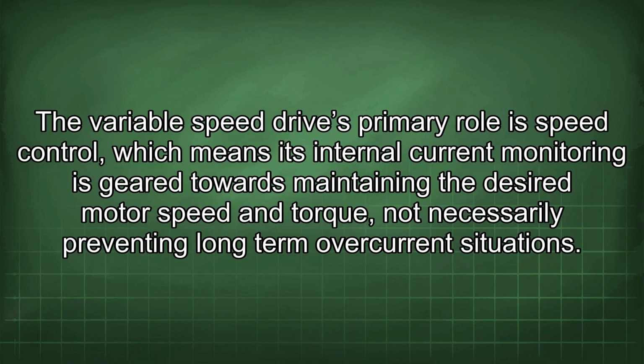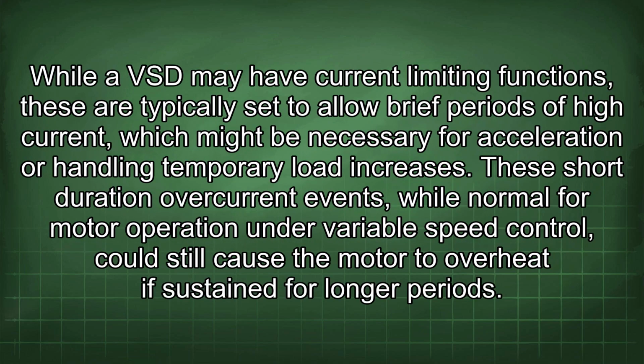The variable speed drive's primary role is speed control, which means its internal current monitoring is geared towards maintaining the desired motor speed and torque, not necessarily preventing long-term overcurrent situations. While a VSD may have current-limiting functions, these are typically set to allow brief periods of high current, which might be necessary for acceleration or handling temporary load increases. These short-duration overcurrent events, while normal for motor operation under variable speed control, could still cause the motor to overheat if sustained for longer periods.